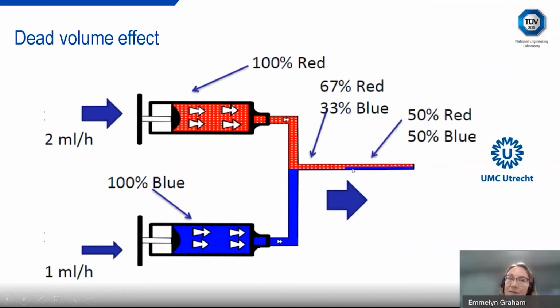But because of the dead volume effect, it still has to push out this 50% red and 50% blue to the patient. So if you have a very long infusion line to the patient, it's going to take a considerable period of time before the increase in the red actually reaches the patient. This is what we call the dead volume effect or push out effect, that time delay, and it's related to the volume in the infusion line.